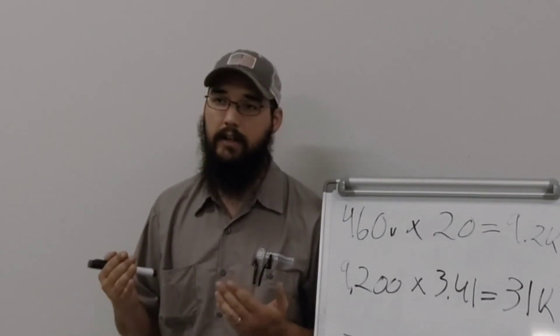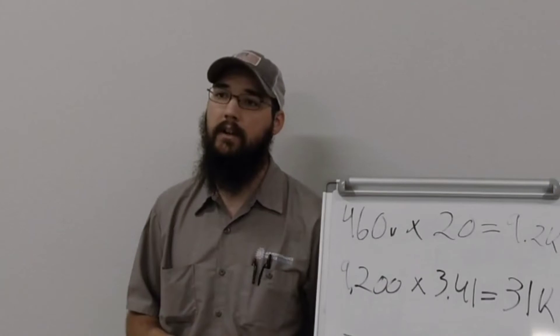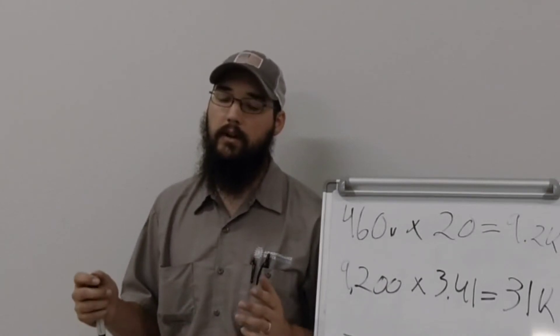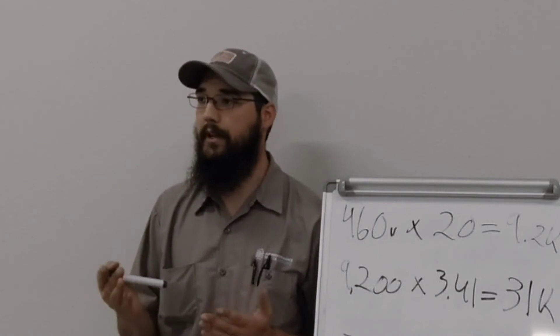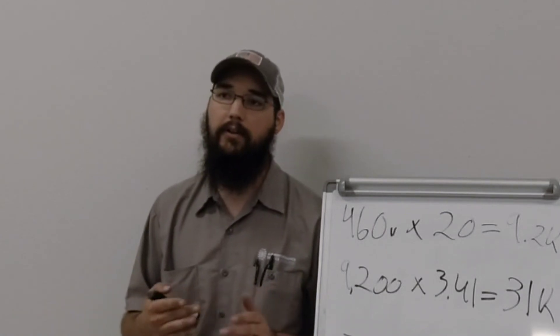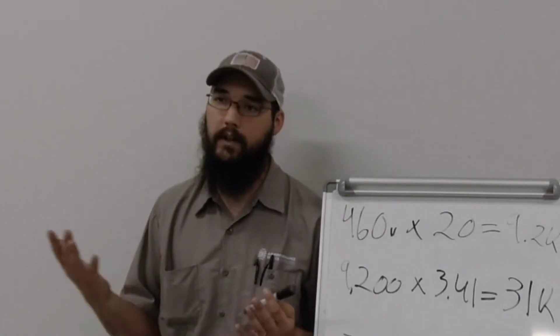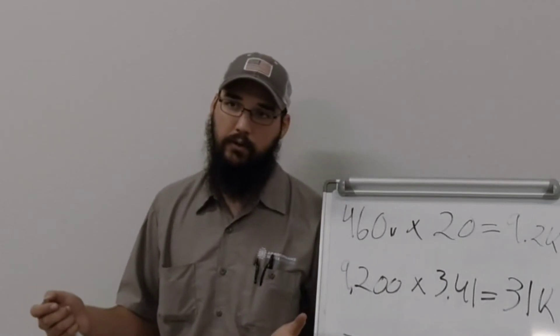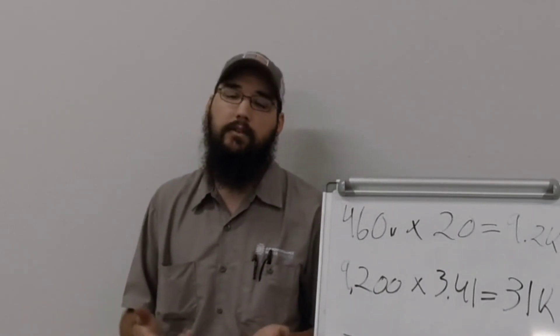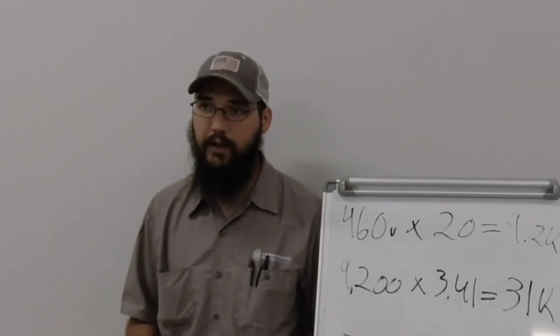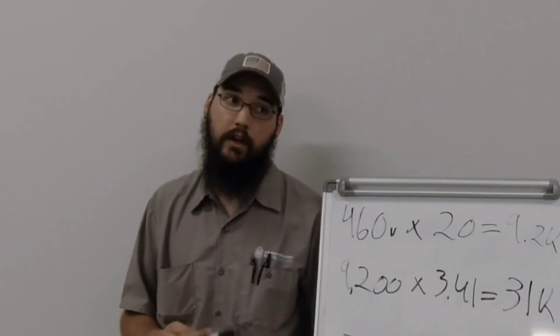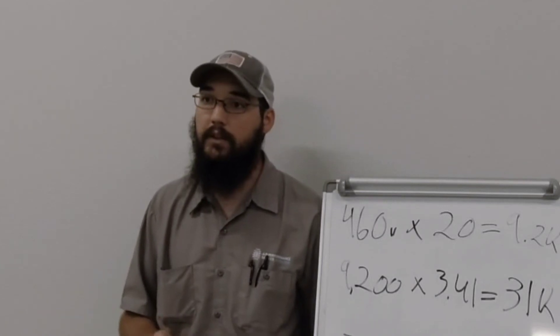We do still run into some systems that are vane, inlet guide vane controlled fans. And so, at that point you're looking at a proportional reading. It's not a hertz factor or percentage, it's how open are they. If they're running 20, 30 percent open, again, that's very little load. If you start seeing 70 percent open, you shouldn't see 100 percent ever. You never want to see that.